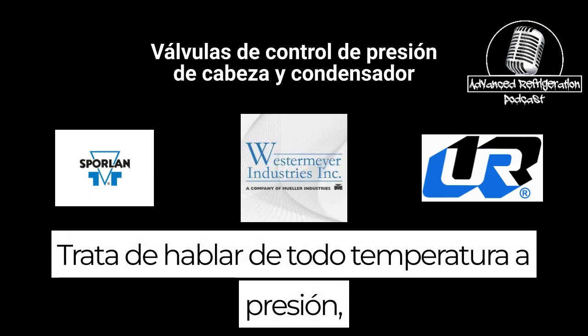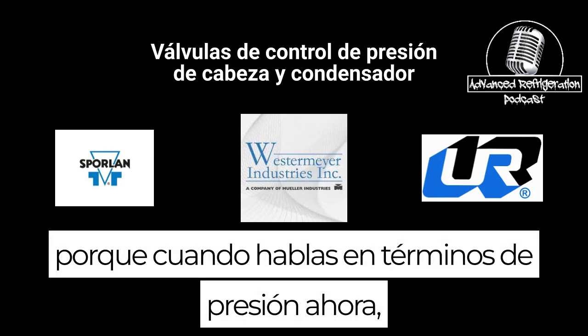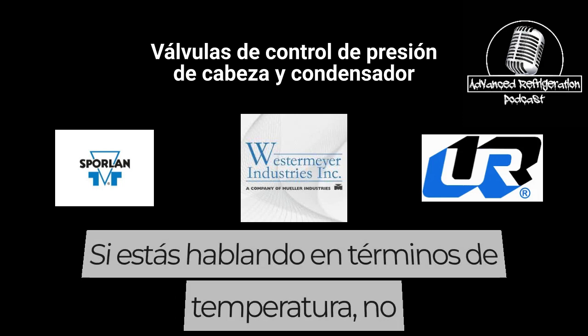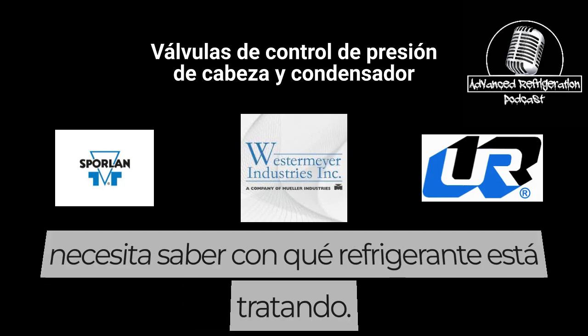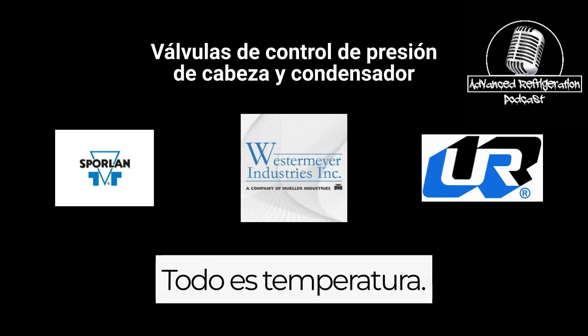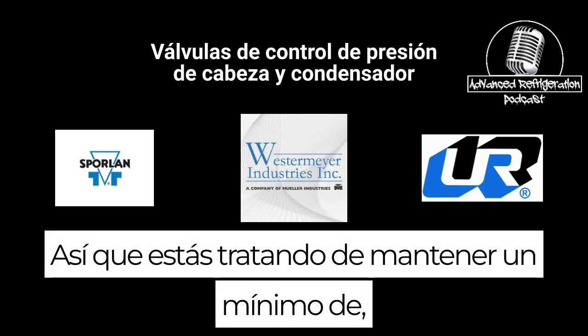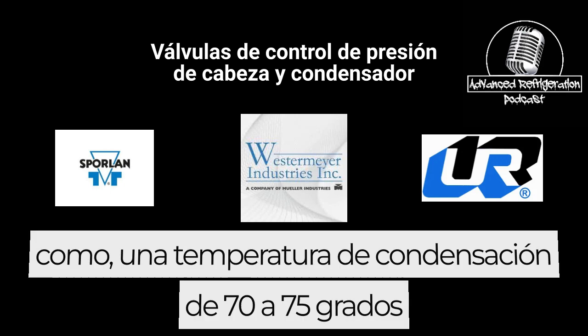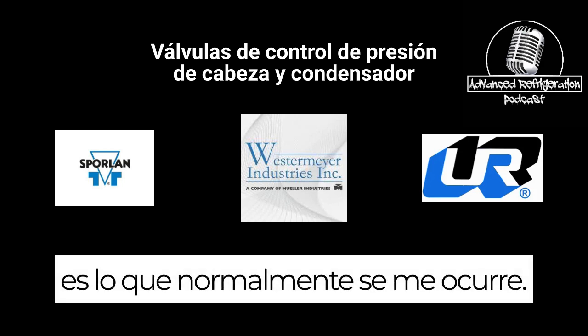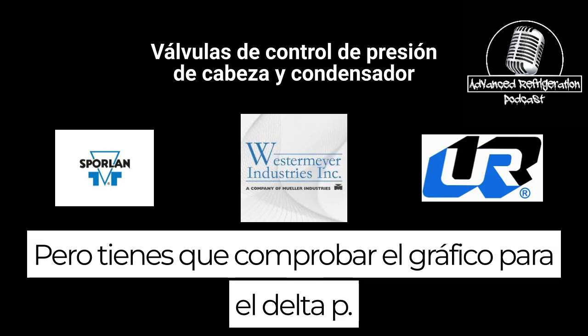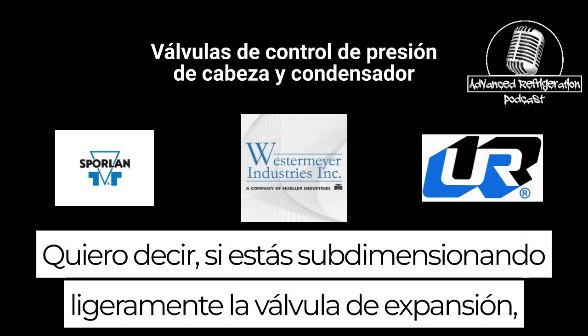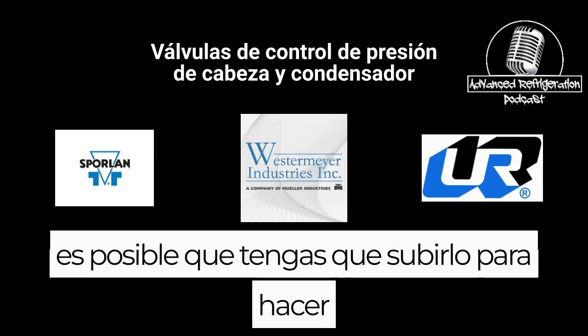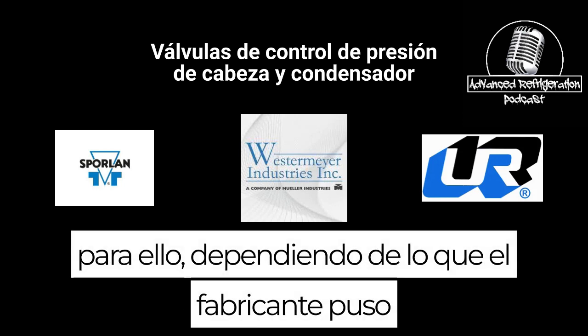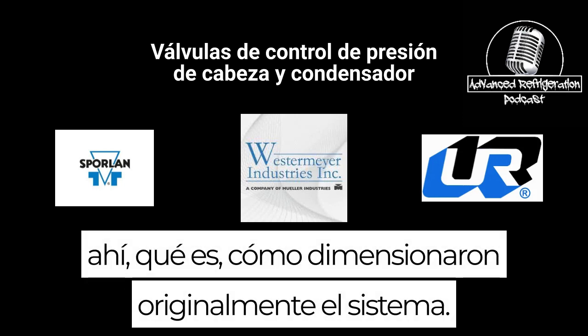Try to talk about everything in temperatures rather than pressure, because when you're talking in terms of pressure, now you got to know what refrigerant you're dealing with. If you're talking in terms of temperature, you don't need to know what refrigerant you're dealing with. It's all temperature. So you're trying to maintain a minimum of like a 70 to 75 degree condensing temperature is what I usually come up with. But you have to check the chart for delta P. If you're slightly undersized in the expansion valve, you may have to bump it up to make up for it, depending on what the manufacturer put in there and how they originally sized the system.